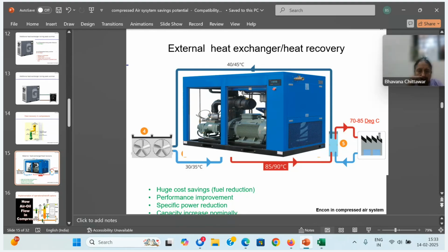So by this, we are achieving 2-3 results. First, we are recovering the entire heat. We can give it to the process or even give it to canteen hot water. If there is no requirement for the process, you give it to the canteen. Have a hot water storage, circulate the water, and give them water for dishwasher cleaning or cooking or whatever it may be. The process, you give it to them, or boiler feed water. So this will be a huge energy you can recover. Then by keeping the radiator heat outside the room, you are keeping the compressor room very cool. So you can save on the compressor energy also. Oil replacement period will get enhanced. Your capacity will increase when air oil temperature is less.